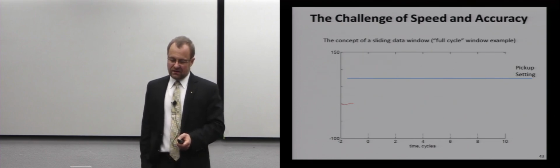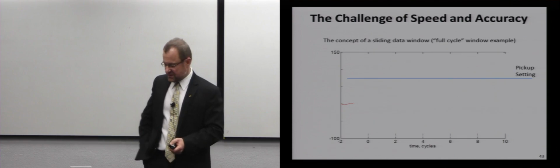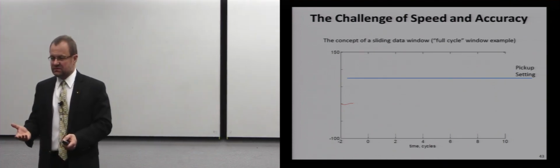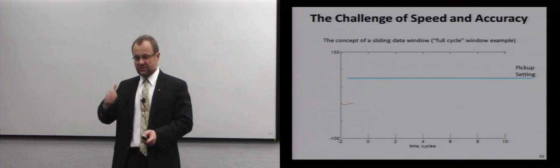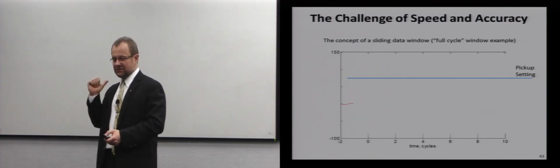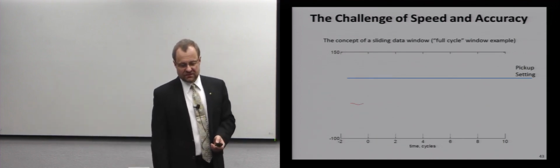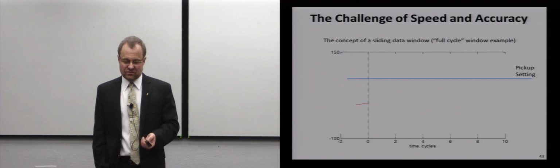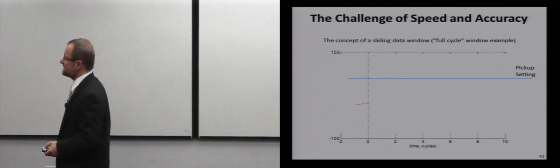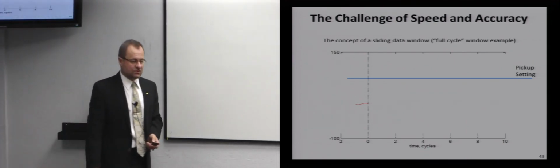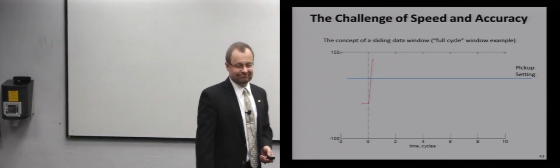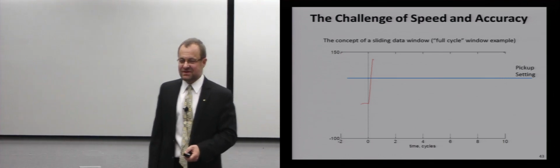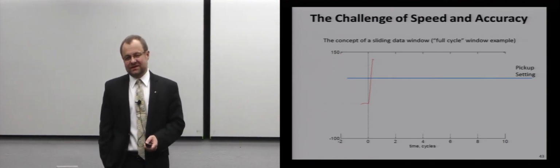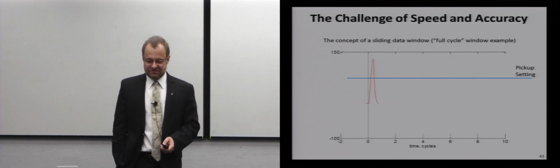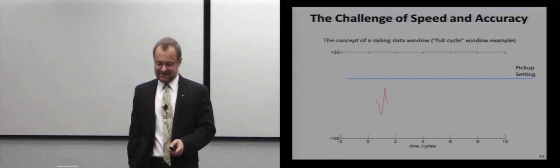Now, to visualize how the relay works, if we are running one cycle algorithms, we look at the one cycle of data from now to the past, right? We don't know the future, we only know the past. So as this data moves, what do we say? Trip or no trip? No trip, right? I mean, no matter how you crunch the data window, this current is definitely lower than the blue threshold, right? No trip. Now, shall I trip? Well, I don't know. I want to be a fast relay, right? I want to beat the competition, but then I don't want to trip when I shouldn't. Shall I trip right now? I don't know. Now, probably would say no.